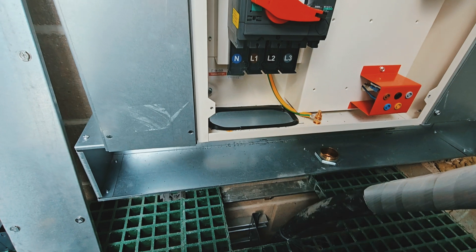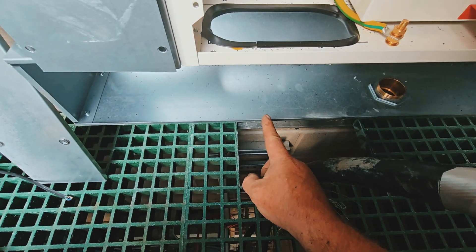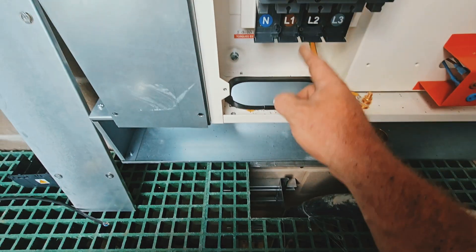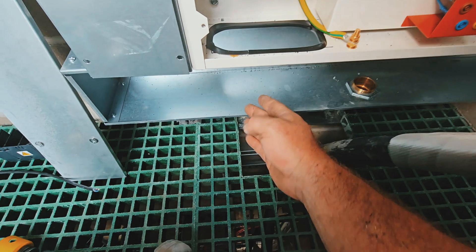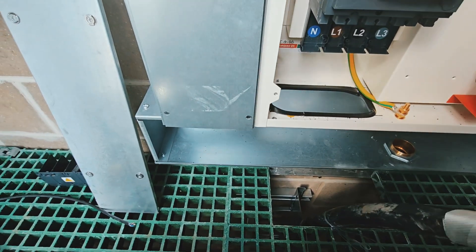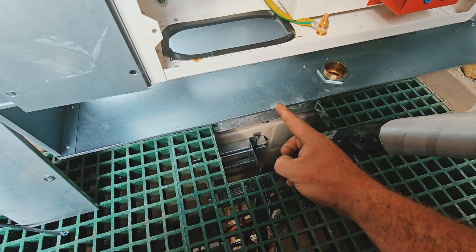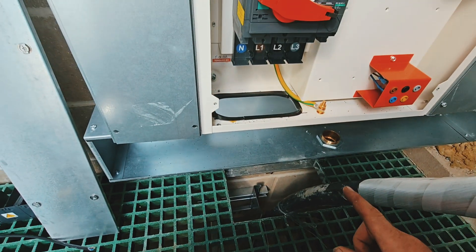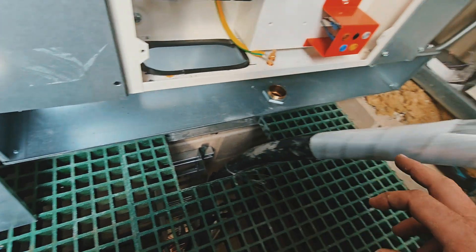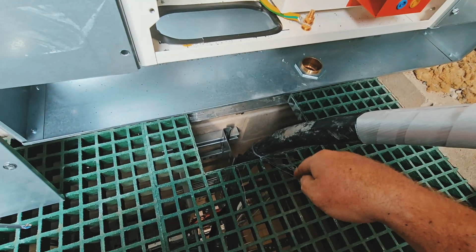This is a four-core 150. It goes into that switch there. The rack comes up here, so if I was going to go on the rack I'd come in directly underneath and straight through this — this is 150 trunking. There's no way I'm bending 150s through there. So what I'm going to have to do is offset it so I can bend them like that and up. I have to take this trunking off and slide it over the top of the cable, like I did with the end cap downstairs.